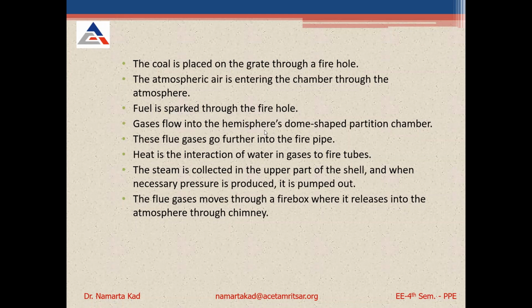Gases flow into the hemispherical dome-shaped chamber. So gases start flowing in the main shell. These flue gases go further into the fire pipes. The gases start flowing through the fire tubes. The heat is transferred from the gases in the fire tubes to the water, and the water around those tubes starts heating up. The steam is collected in the upper part of the shell, and when the necessary pressure is produced, it is pumped out for the turbine work.